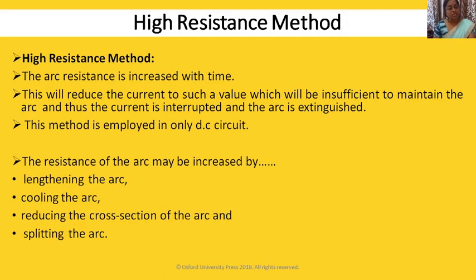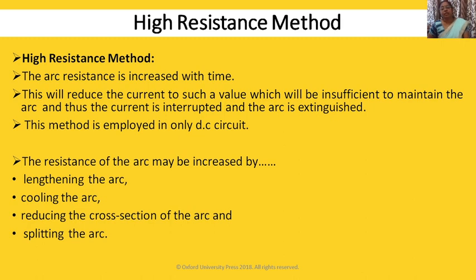In the high resistance method, the arc resistance is increased with time. This will reduce the current to such a value which is insufficient to maintain the arc, and thus the current is interrupted and arc is extinguished. If you increase the resistance, the current will reduce and that is why the arc gets extinguished. This method is employed only in DC circuits, as DC has a constant waveform.